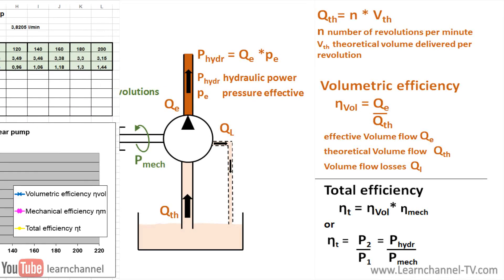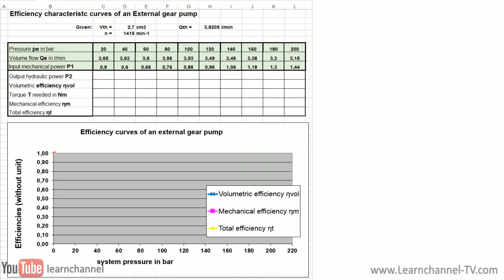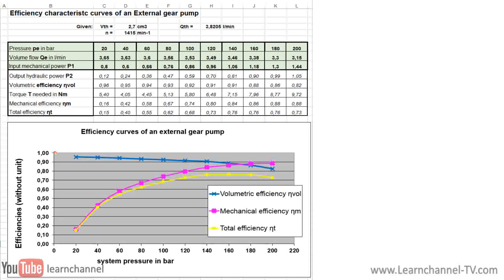The following measuring table shows the volume flow and the mechanical input power in dependence to the system pressure. The other values you can evaluate. What you see is that the volumetric efficiency is getting worse with growing pressure. And of course, the total efficiency curve must always remain under the other curves.